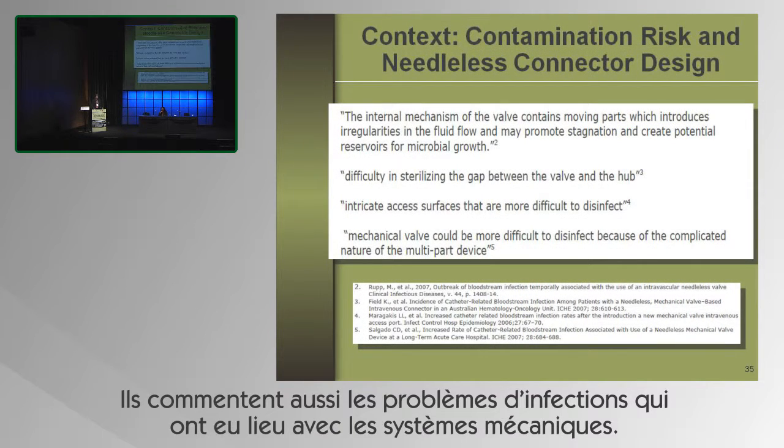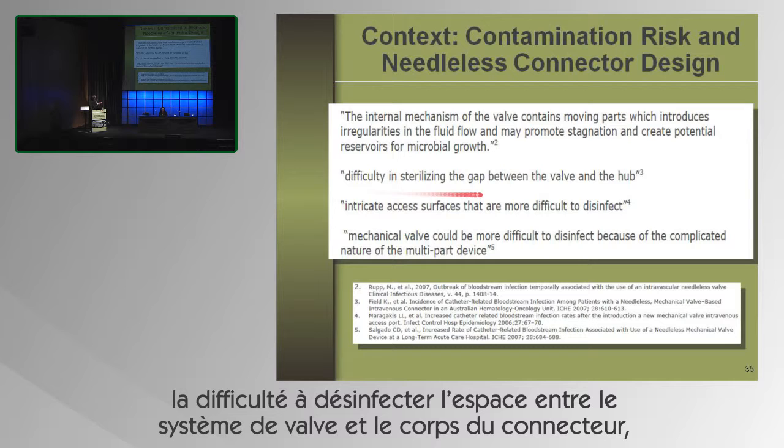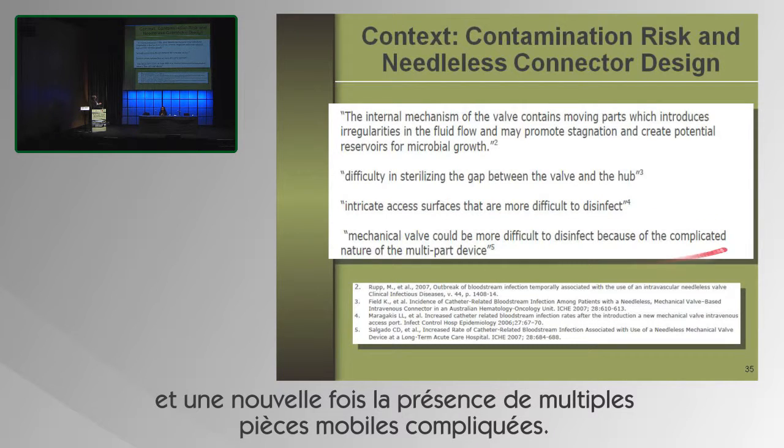And again, they comment on a number of the outbreaks that have occurred and point out the importance of the internal mechanism, the difficulty sterilizing gaps in the valves, the intricate access surfaces that are difficult to disinfect, and again, complicated, multiple moving parts.